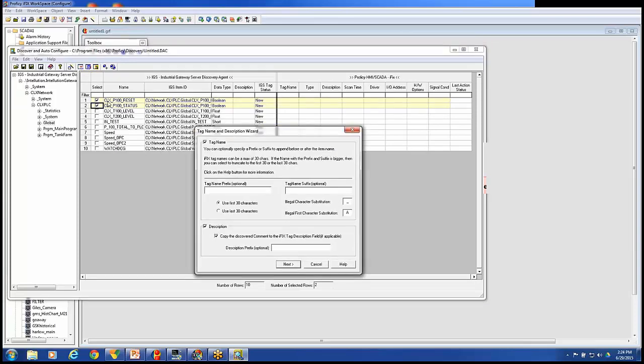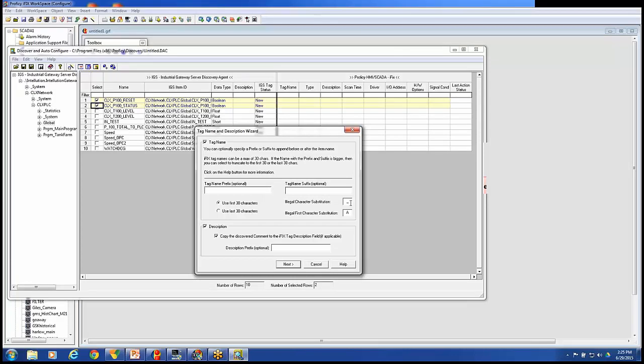See that currently it's going to bring the tag name over just like this. CLX P100 reset and CLX P100 status. I could add a prefix to it or a suffix to that tag name when it brings it over. If there were illegal characters here like slashes, question marks, I can change those to underscores. If it was longer than 30 characters, I would have to truncate it. And I could either grab the first 30 characters or the last 30 characters. And illegal first character substitution. If this started with a number or a pound sign, anything other than a letter basically, we would replace that with a letter, the letter A. And I could also prefix the description when it moves over a description.